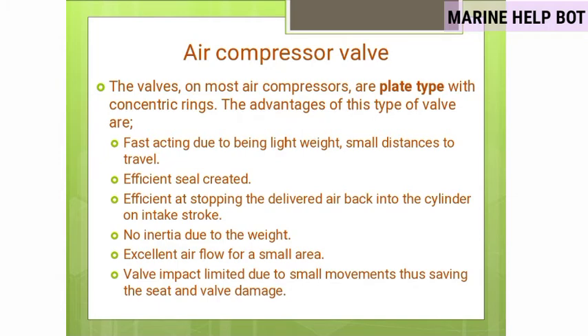Why are plate type valves used on marine air compressors? The valves on most compressors are plate type with concentric rings. Advantages include fast acting due to being lightweight, small distances to travel, efficient seal created, efficient at stopping delivered air back into the cylinder on intake stroke, no inertia due to weight, excellent airflow for a small area volume, impact limited due to small movement, saving the seat, and less valve damage.